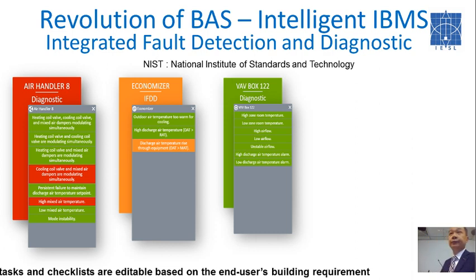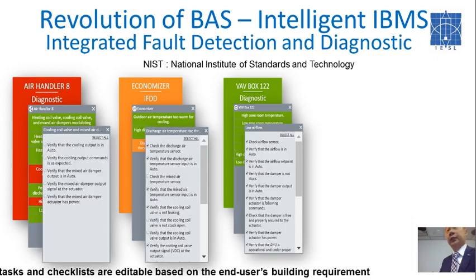So rules are written. The building BMS companies will talk to consultants and understand from the building owners which equipment is going to be installed, whether commercial or industrial, and what is critical to monitor. So we write rules based on his needs, followed by the checklist. There's communication between all three parties, and this isn't fixed - once the building load increases or reaches 100% with equipment and occupants coming in, the building behaves differently. So we edit the rules and the checklist to optimize.